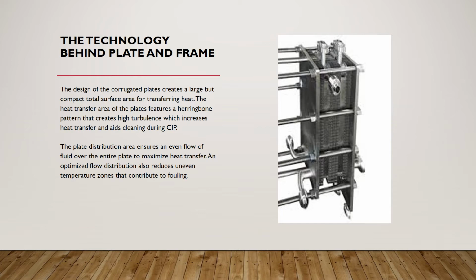The heat transfer area of the plates features a herringbone pattern that creates high turbulence, which increases heat transfer and aids cleaning during CIP. The plate distribution area ensures an even flow of the fluid over the entire plate to maximize heat transfer. An optimized flow distribution also reduces uneven temperature zones that contribute to fouling.